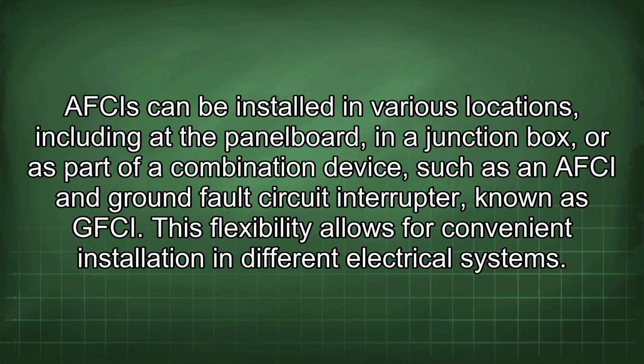AFCIs can be installed in various locations, including at a panel board, in a junction box, or as part of a combination device, such as an AFCI and ground fault circuit interrupter, known as AFCI/GFCI. This flexibility allows for convenient installation in different electrical systems.